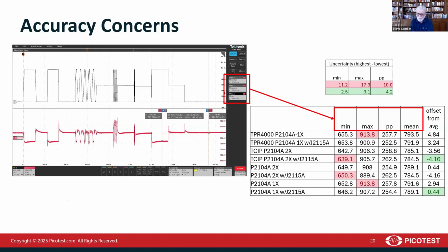This is just probes. And so one of the things that we're going to have to deal with is how do we deal with the uncertainty that's really large? And in our own measurements, what we noted was that there were two in particular that were really close together, in fact, within about 3 or 4 millivolts. And that was the TCIP probe and the Picotest P2104 probe using a coaxial isolator. And what that would suggest is that a big part of this error is ground bounce error and how the ground bounce error gets into the probe measurement.